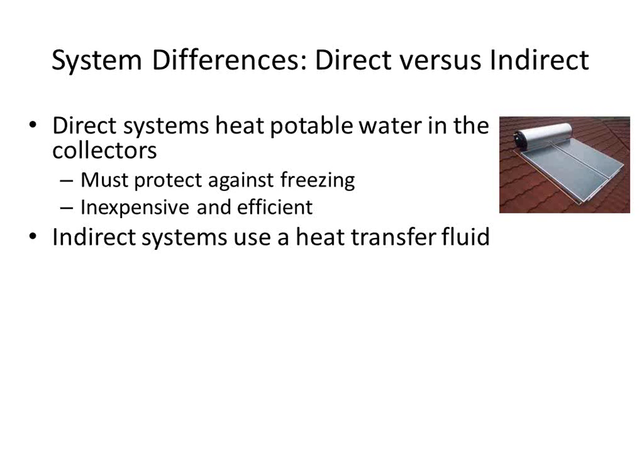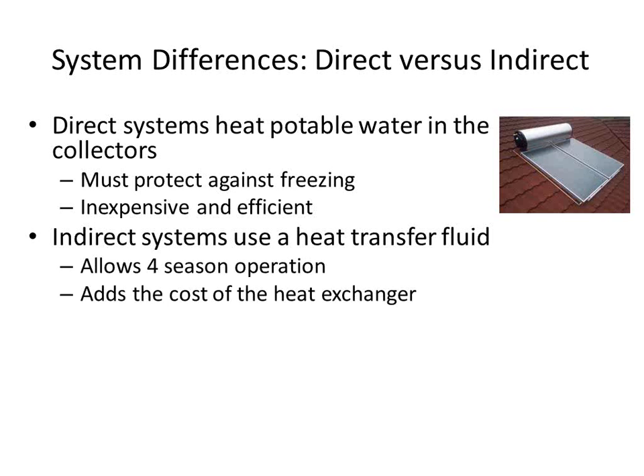So for that reason, indirect systems are much more commonly used in the U.S., and particularly in the sort of northern half of the U.S. They allow four-season operation. The downside is that they do cost more. You have to add a heat exchanger, you have to have the glycol itself, and the system, due to the lower heat transferability of glycol and the decrease in efficiency through the heat exchanger, the systems aren't as efficient, so you end up having to add some collector area.